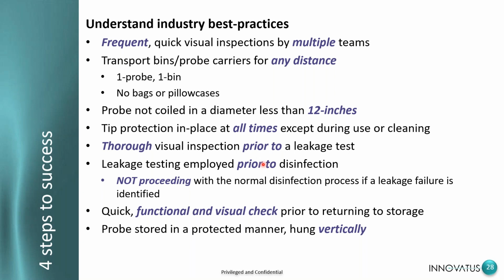If we fail a leakage test, in all likelihood, you have a breach in the probe. You want to remove the probe from service at that point. Wipe it down with a disinfectant wipe that has been approved by the OEM, but get it in a box, get it off to us. We'll get the repair done. As I mentioned earlier, the difference between a low-level repair, a hole in an insertion tube or a hole in a bending rubber, versus fluid invasion, if you energize the probe, is exponential. And so if you fail a leakage test, pull the probe, wipe it down if you can with an approved disinfectant, but do not soak it, do not energize it any further. Get it in a box and get it back to us, and we'll get you taken care of.